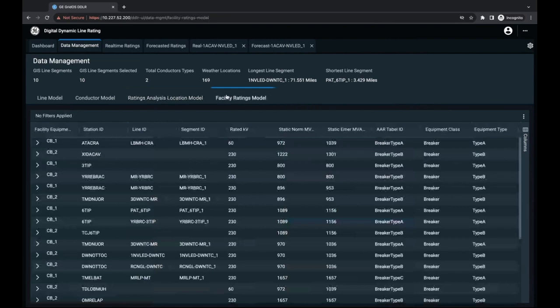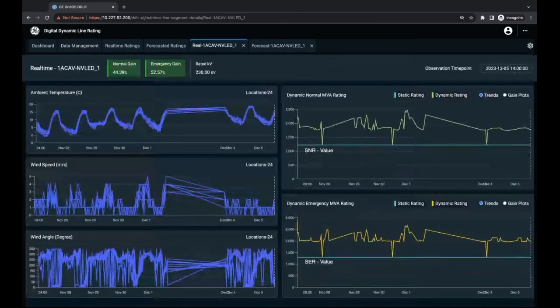And last but not least, we also cover the facility ratings, so we can get really deep into the substations and find other limiting factors that could limit your performance or capacity across the network. If you click on real-time ratings, we'll have the ability to see real-time data coming in as we operate now, and in the short-term future, what's going to happen in the next 24 hours. You can see the operating lines and the normal ratings and emergency ratings, as you can see on the right-hand side.